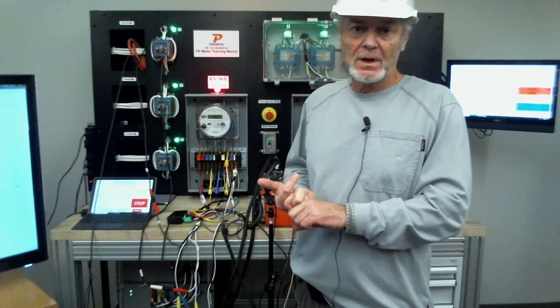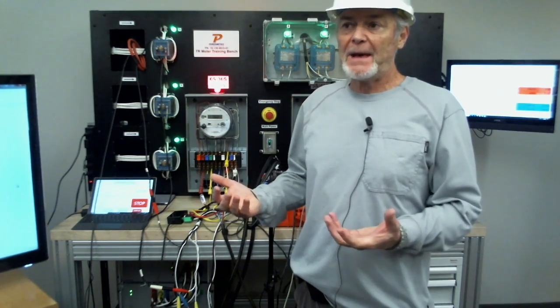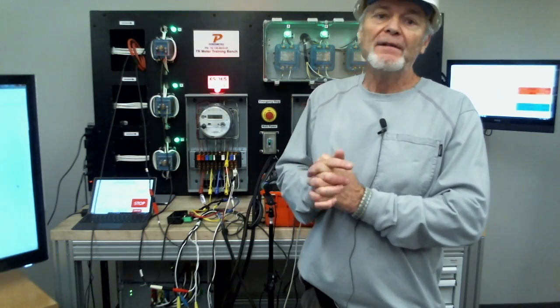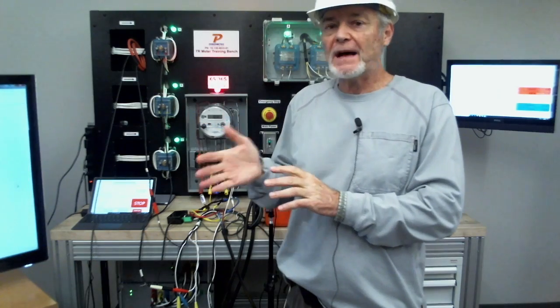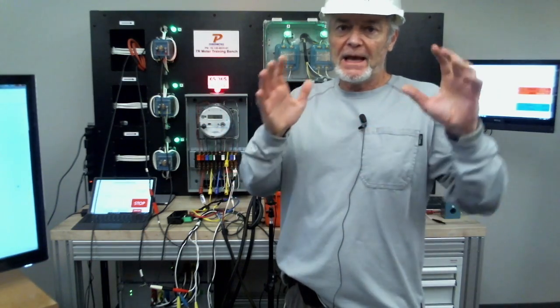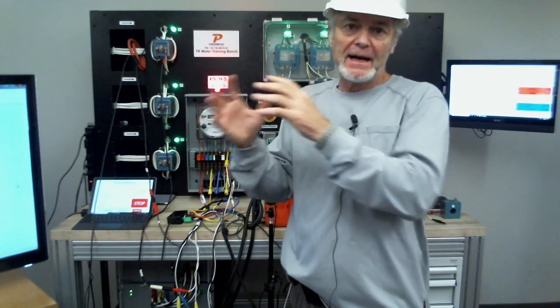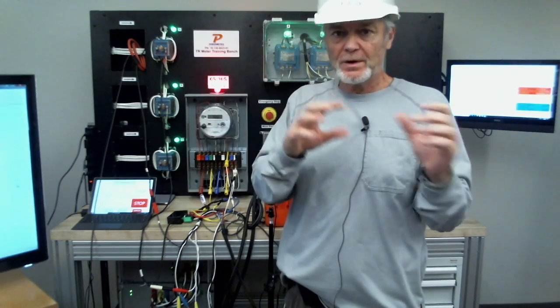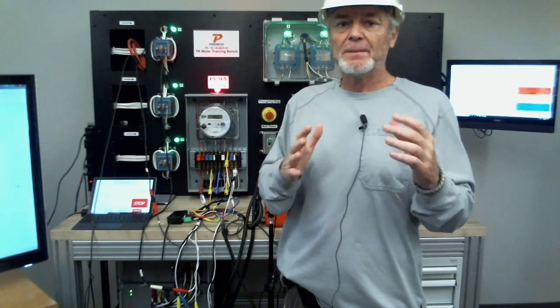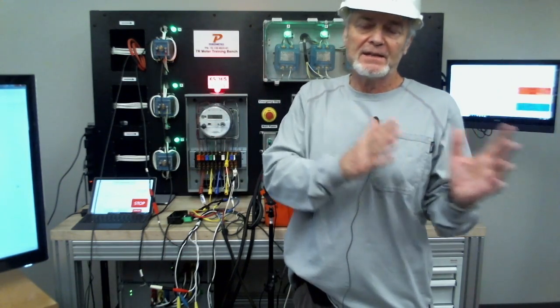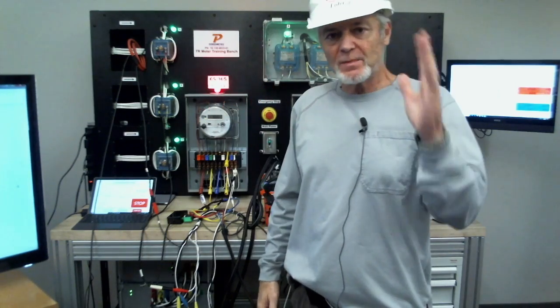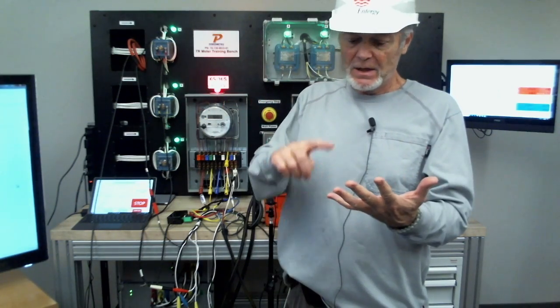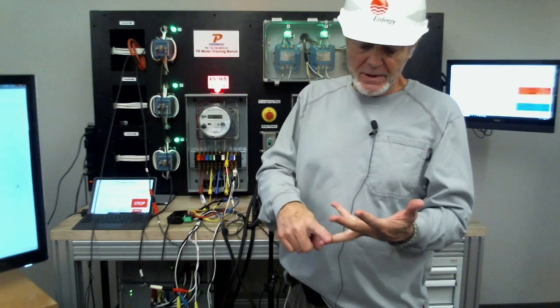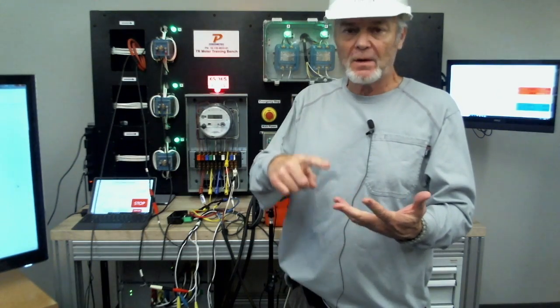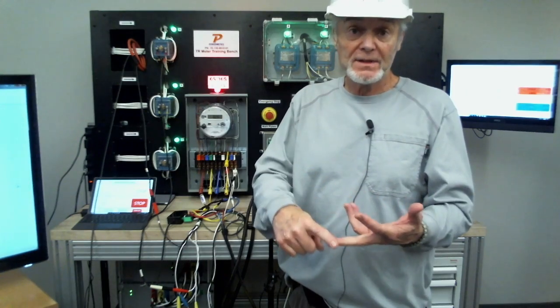So if they're underloaded, they don't do us any good. Like we've said in the past, the number we use is 0.5 secondary amps, because remember, everything on our CTs is always to 5: 200 to 5, 400 to 5, 800 to 5. So if I need 10% on the primary side, that's 20 on a 200, 40 on a 400, or 80 on an 800. On the secondary side, it's always 0.5 every time, because it's a tenth.